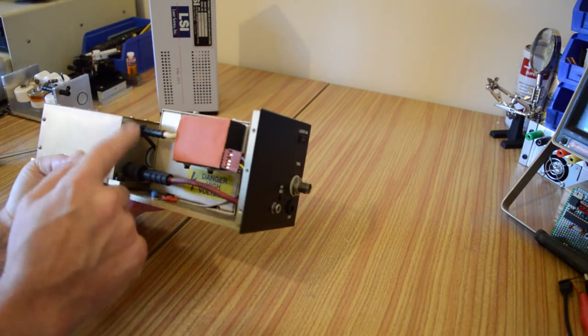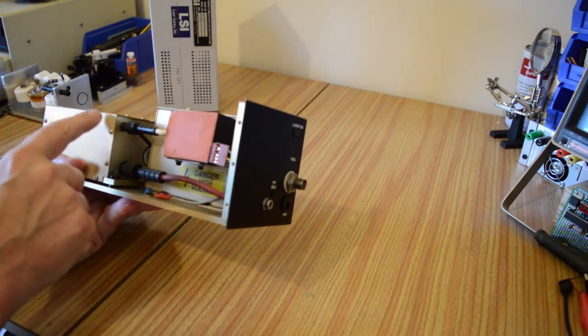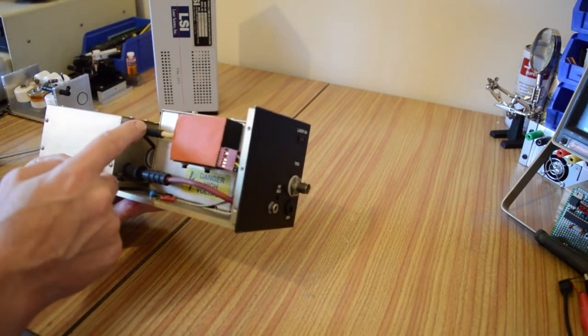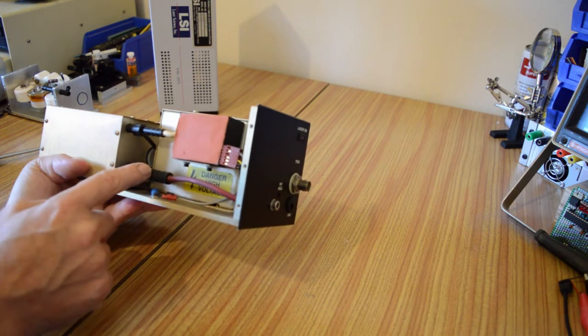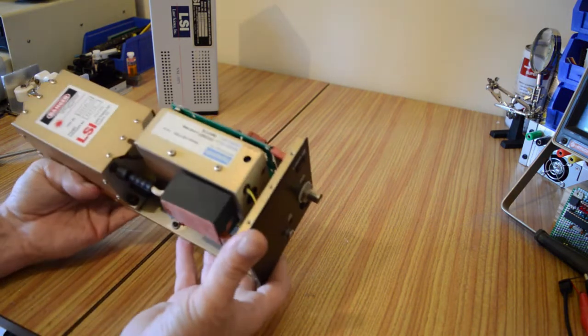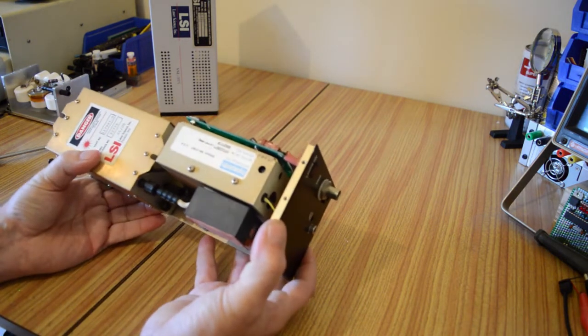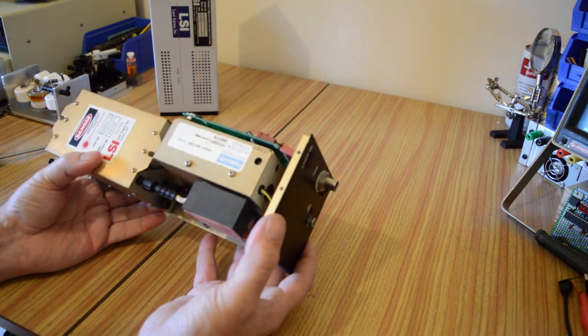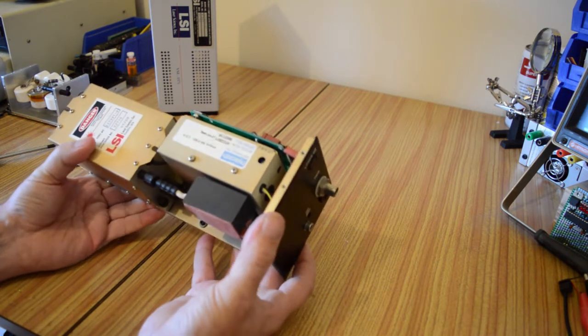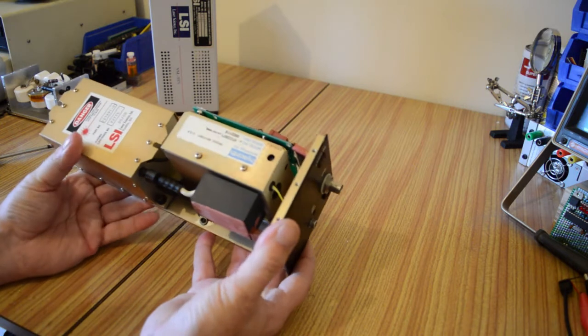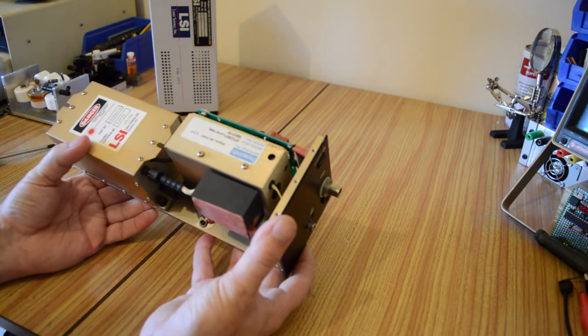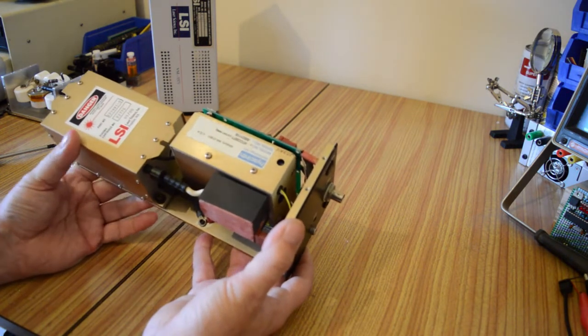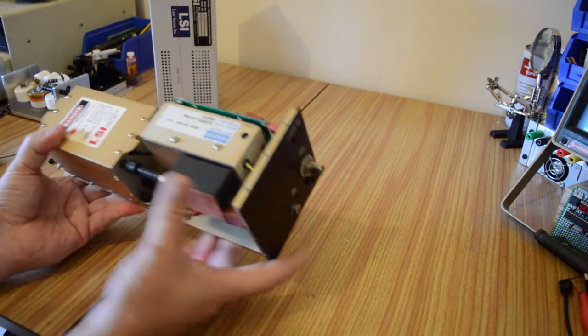So we can see we've got two main connections to the tube itself. We've got the trigger voltage in and then we've got high voltage connection down at the bottom. In terms of voltage, the voltage that we actually charge the tube with in here is around about 17 and a half thousand volts. But it's at a very low current, so I don't think that you would stand very much chance of electrocuting yourself with it. That said, accidents happen.